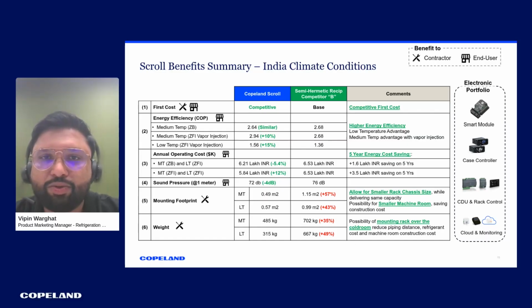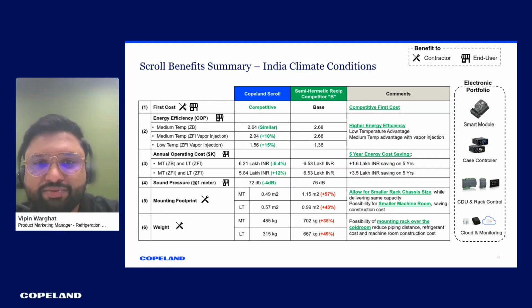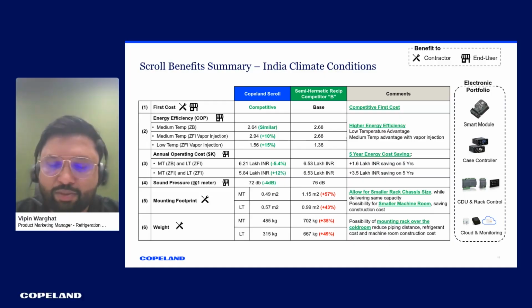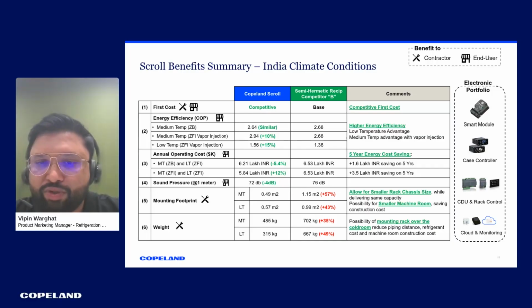Yeah, so this is the overall benefit for the contractor and end user. First cost is very competitive against semi-hermetic. If you have a requirement, we can get into a discussion and discuss that in more detail. Efficiencies were 10 to 15% better versus semi-hermetic compressors, and of course 6 to 12% savings in terms of annual operating cost. And definitely, to sum up, there are additional savings in terms of footprint, weight, and system reliability. If we move on to the next one.